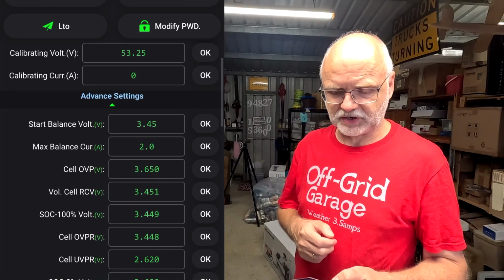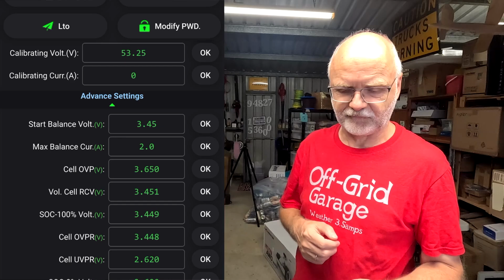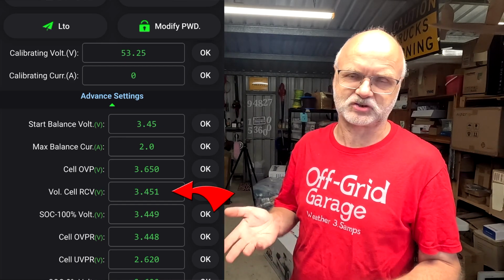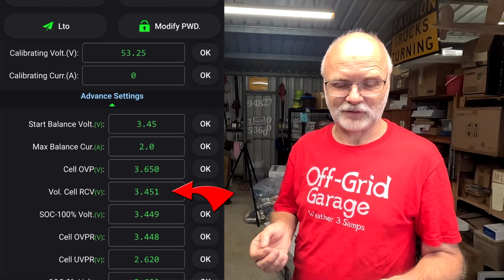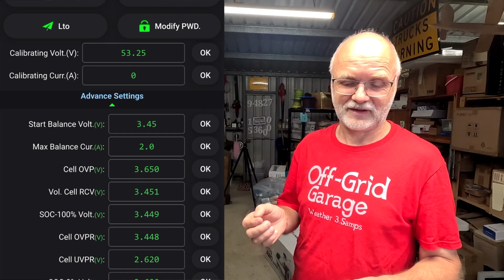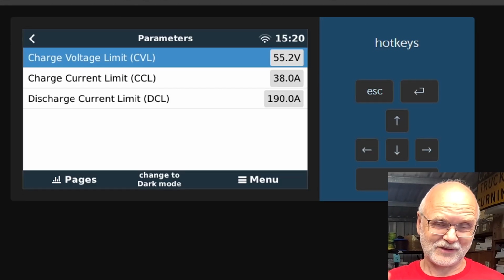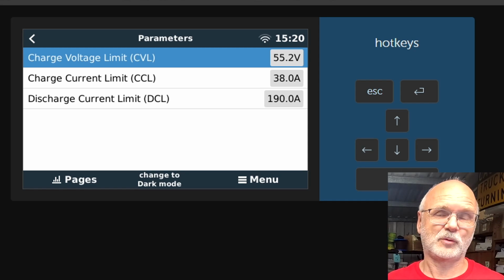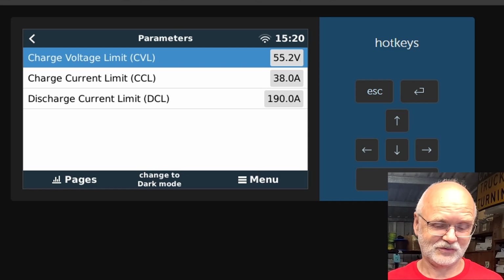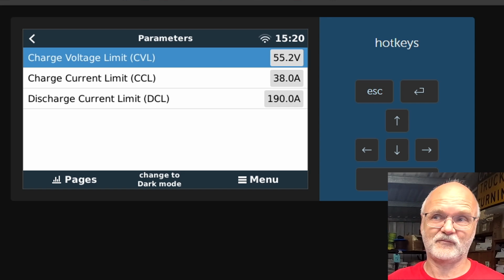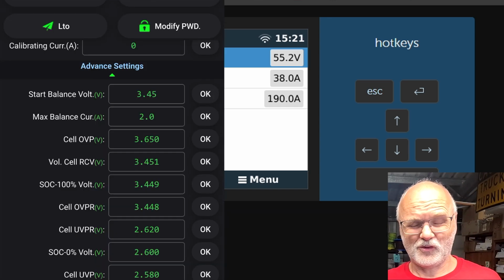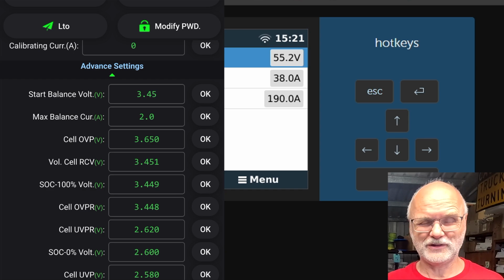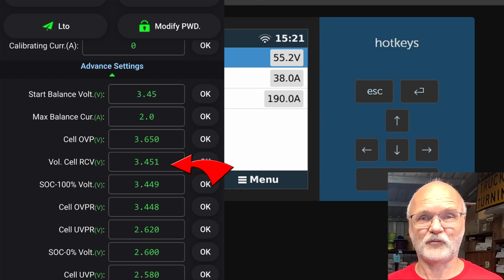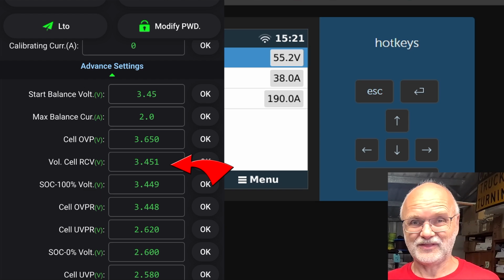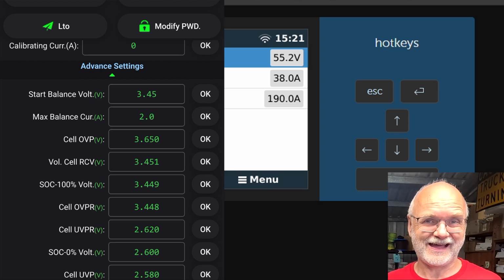So in the JK BMS we have the voltage cell RCV, the requested charge voltage, which in my case sits at 3.451 volts, which, as you've already seen, is 55.2 volts in the Victron system or your inverter. So the inverter will charge to 55.2 volts. For whatever reason, I was under the false assumption that one single cell reaching 3.451 volts is enough to trigger the RCV timer.